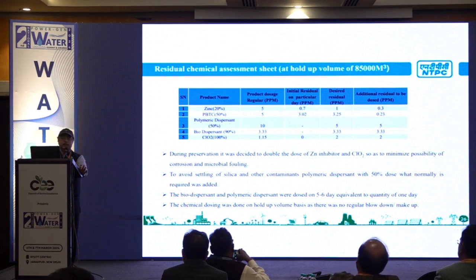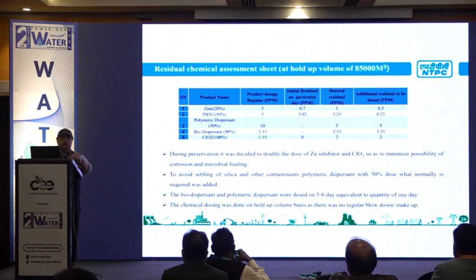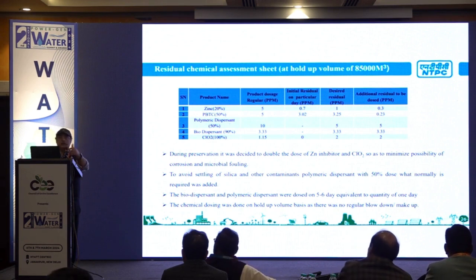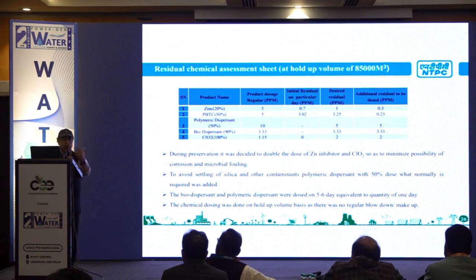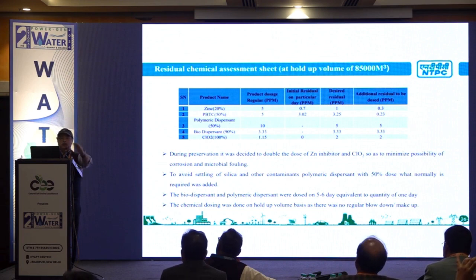To maintain that, we monitor the chemical parameters. Suppose we dose on a particular day whatever is required, then circulate this water through the condenser for 1 day only. There is some increase in auxiliary power consumption, but then for 5 and 6 days those chemicals remain in the system and start decreasing. Then every 5th, 6th or 7th day, depending on residual chemicals like zinc, PBTC etc., we dose an additional amount to maintain our minimum dosing level.